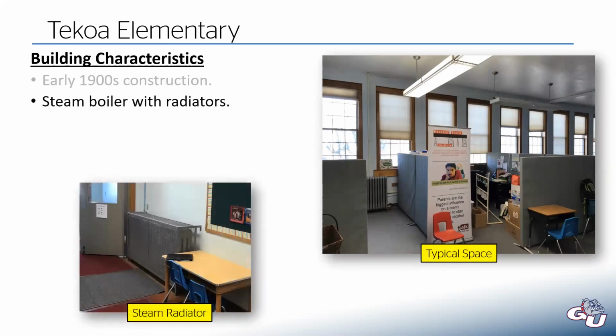Their HVAC, all they had was a single steam boiler with a bunch of radiators throughout the building. I don't have a schematic of this, but basically the boiler makes steam, and then throughout the building you have a bunch of steam piping, which eventually comes to these radiators. And as the steam sits in these radiators, they radiate heat. And that's really all there is to it. It's a very simple system in concept. You can see another radiator here in this office space, but that's all they had through this building.